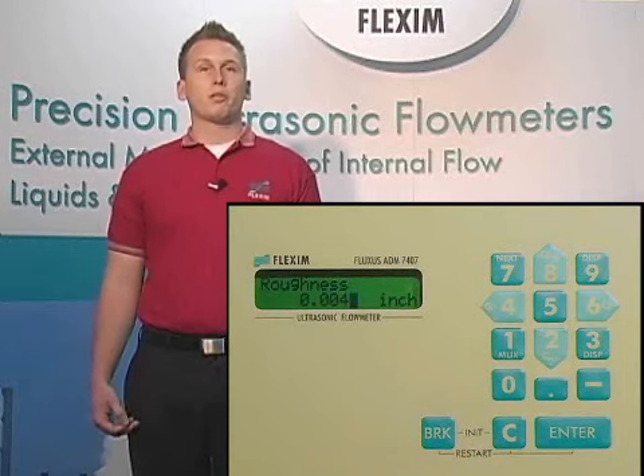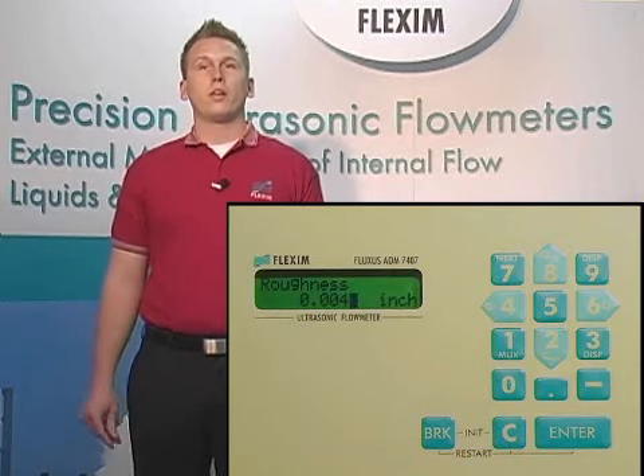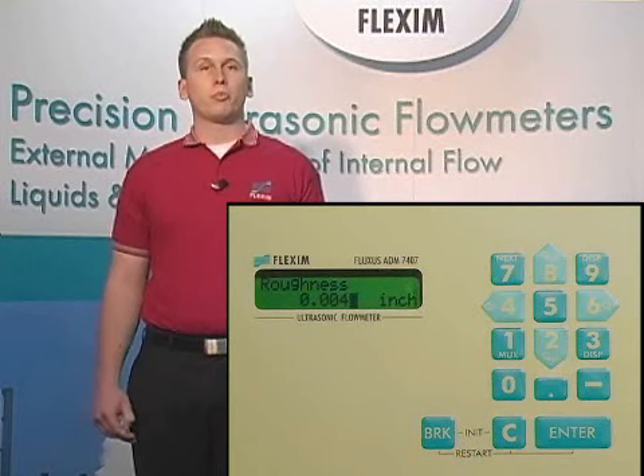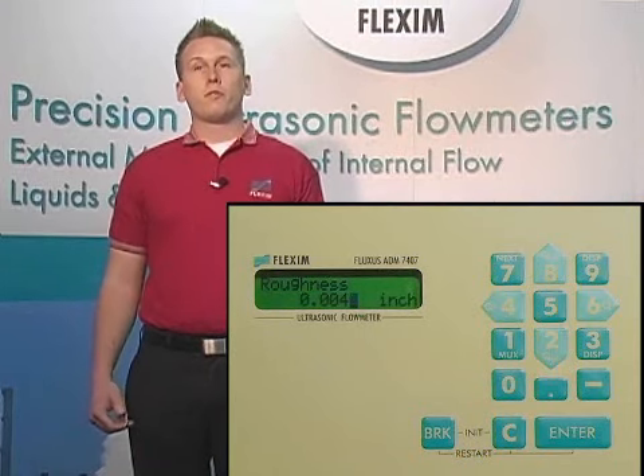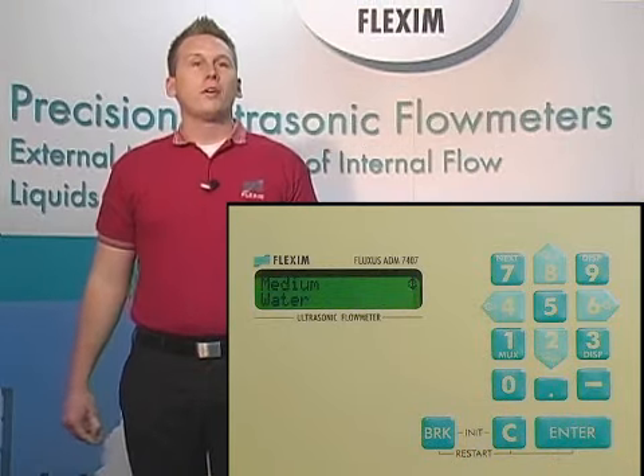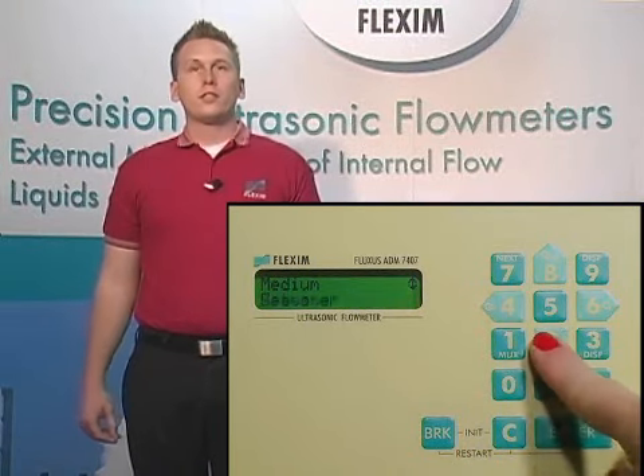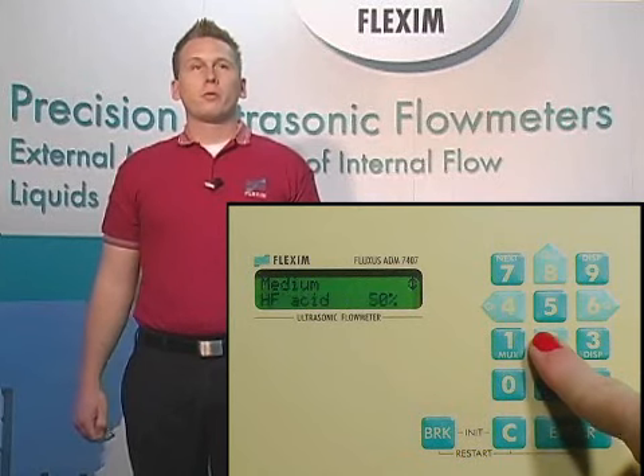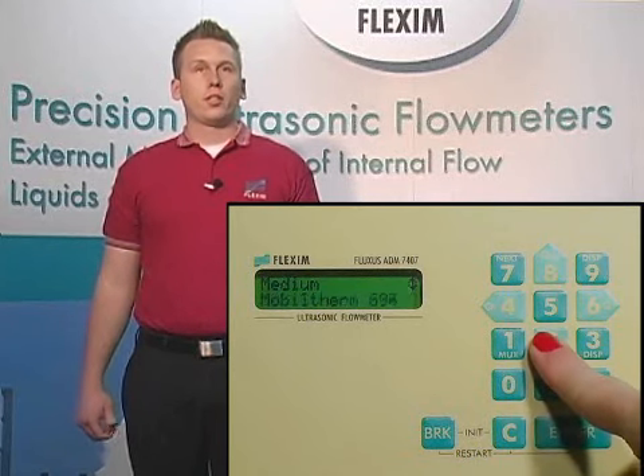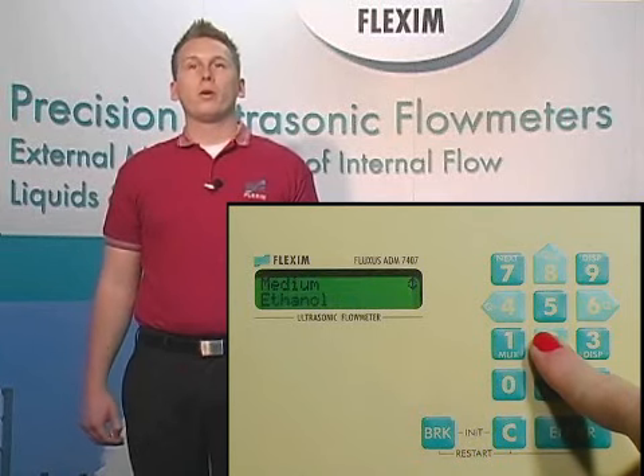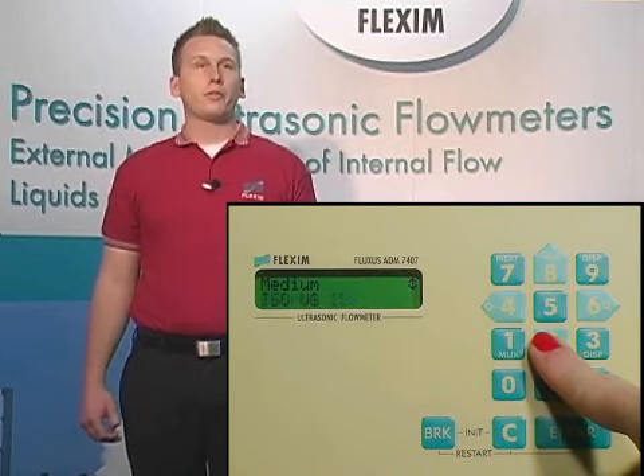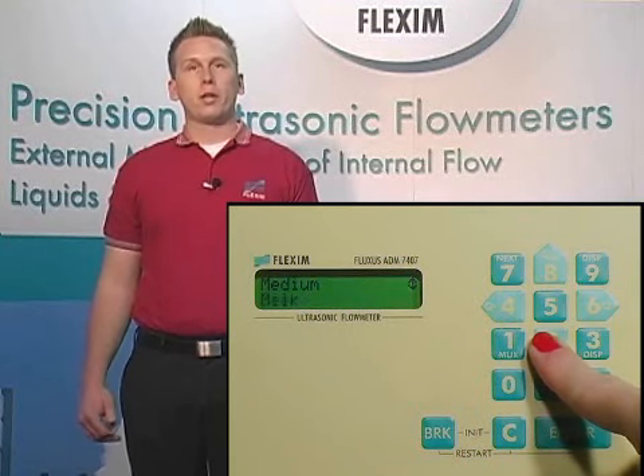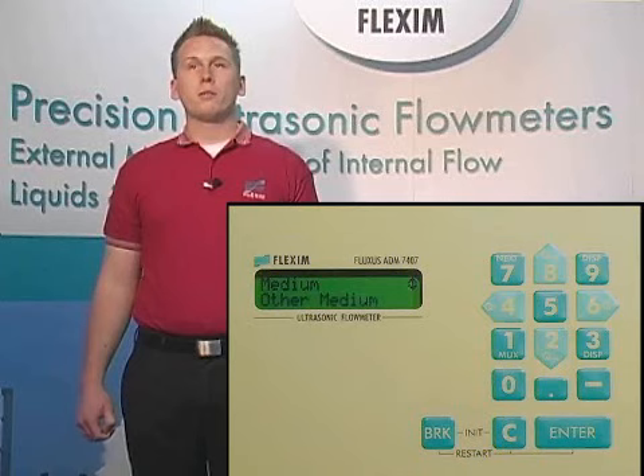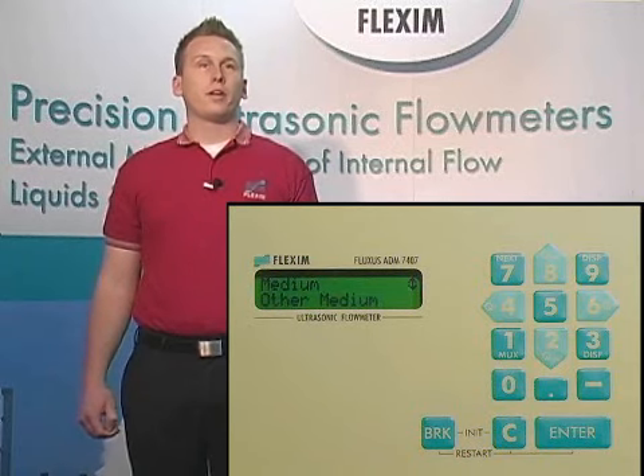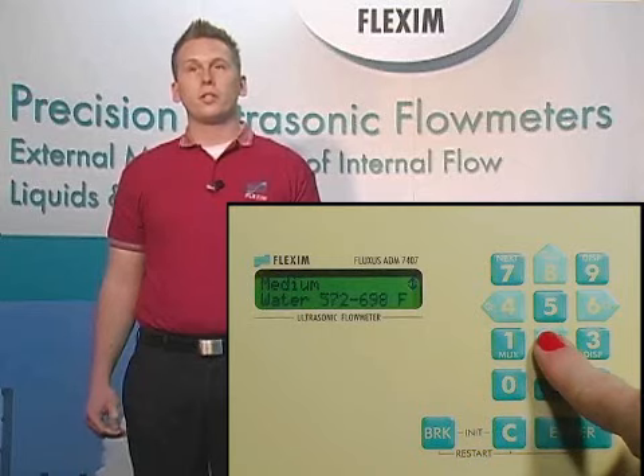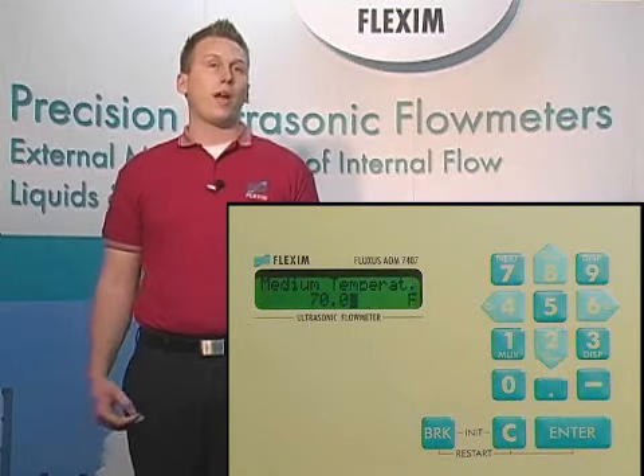Roughness is a measurement of the microscopic imperfections in the surface of a material, and our database has average values for each material by default. We can simply leave the default value alone and hit enter. We're now asked which medium we're measuring. This is the liquid in your pipe. Choose the liquid we want to measure from our extensive list and hit enter. For this example, we can choose water, but we also have many other liquids such as high and low API crude, beer, Mobiltherm, and many more. Also, if you don't see a medium listed that you'd like to measure, contact a Flexim representative to find out how we can install new mediums into your meter for you, either before or after your purchase.